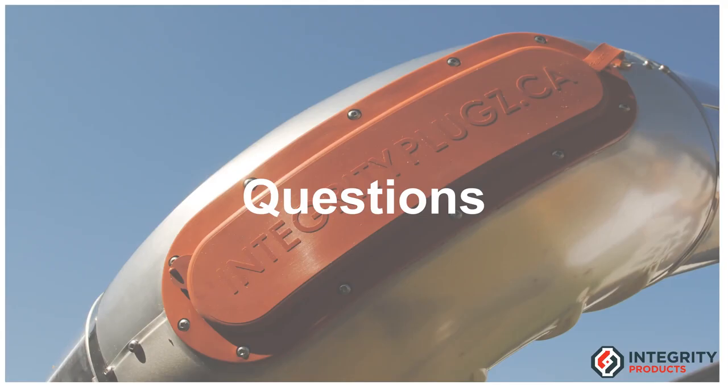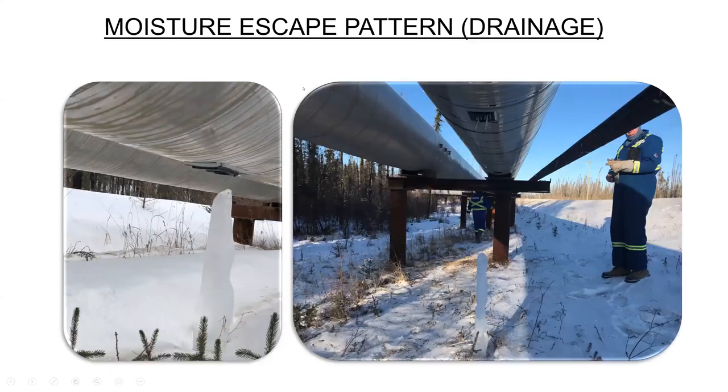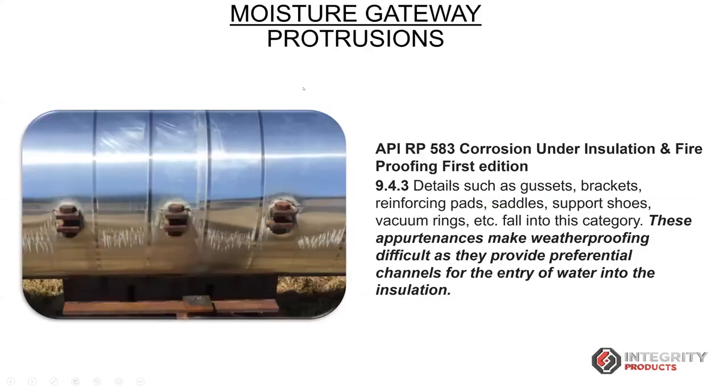So yes, I think traditionally, Ahmad, if you can imagine a cyclic temperature system where your temperatures are fluctuating and you've got condensation built up on the pipe, a lot of the time that moisture and that condensation will vaporize through the body of the insulation. So once it starts to reach the outside of the cladding, what's it going to do? When it reaches the cold inner surface of the cladding, it's going to recondense and form moisture. So again, if the cladding is trapping that moisture in the system, it's going to soak back into the insulation, which will eventually contact the pipe.